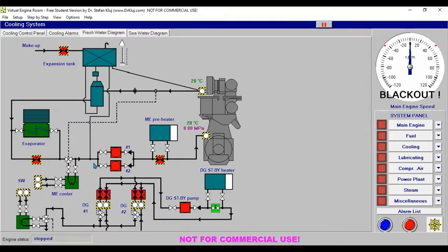We also need to fill our expansion tank for diesel generator number one. Take note: based on the instruction, the expansion tank requires water treatment to avoid corrosion of the main engine and auxiliary engine — also known as jacket cooling. You can see the level rises easily to at least 90 percent. When it overflows, the wastewater just goes to the engine room.